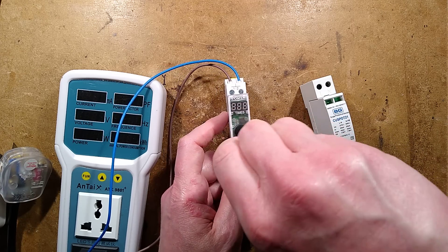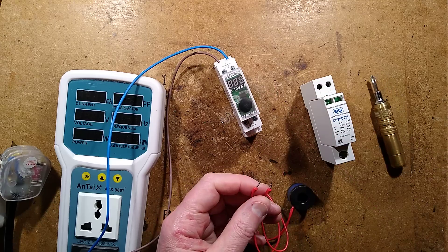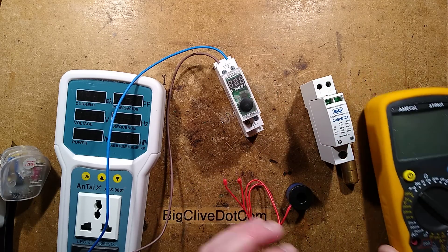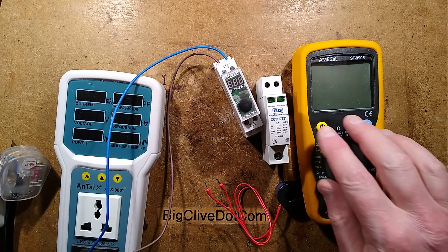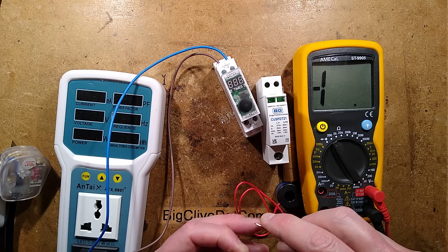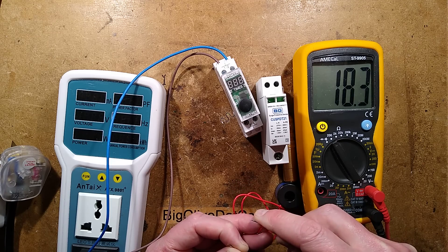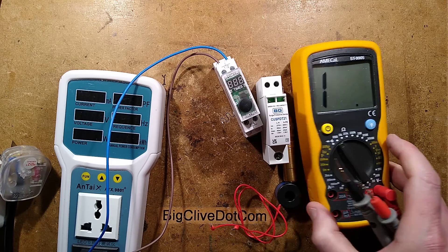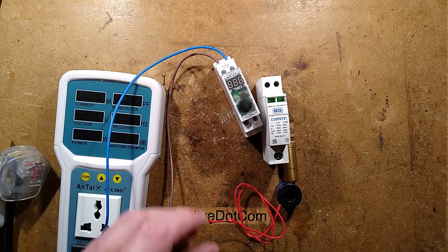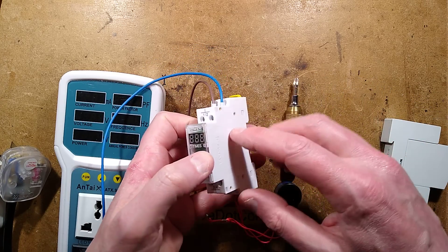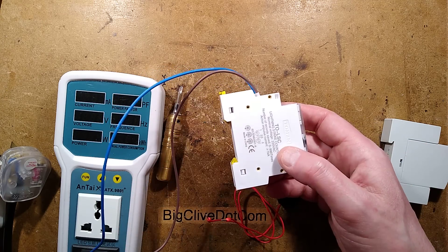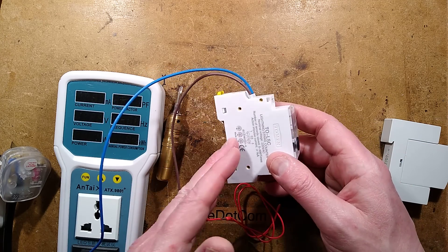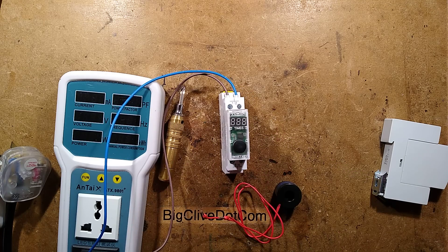This current sensor transformer has quite a low resistance. Let me bring in the meter set at 200 ohms, and it has a resistance of about 18 ohms - very low impedance for the current sensor transformer. Anyway, I'm going to pause momentarily because this thing is held together by rivets. Unfortunately, when I tried to drill these rivets out live, they always end up starting to spin inside the housing. So I shall open it and then we can resume from that point.